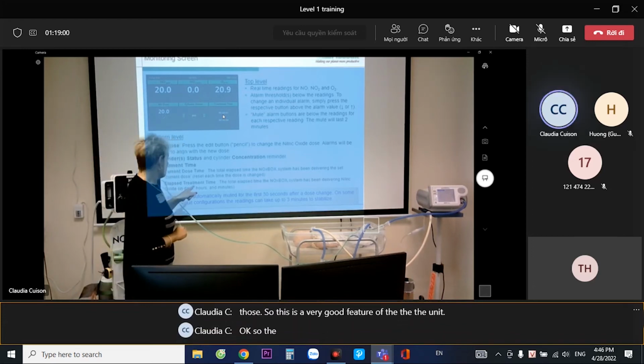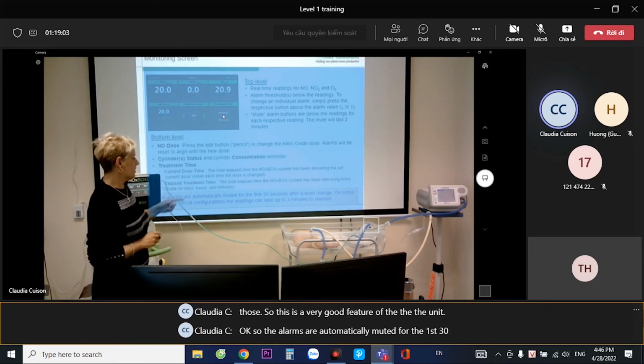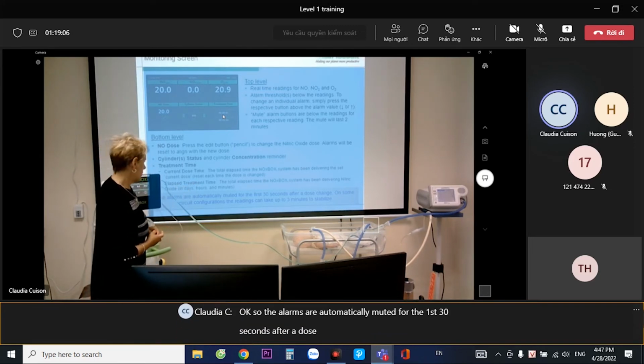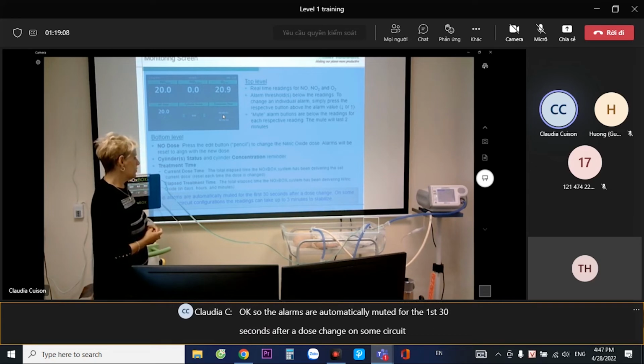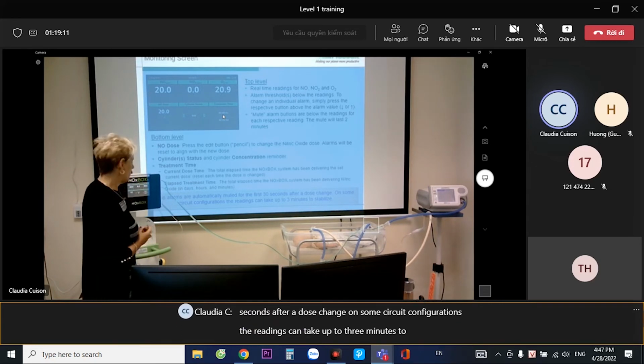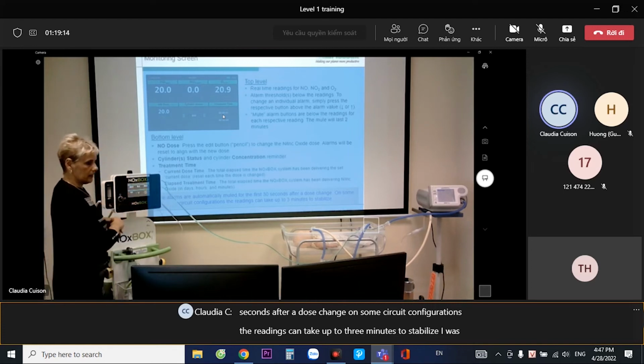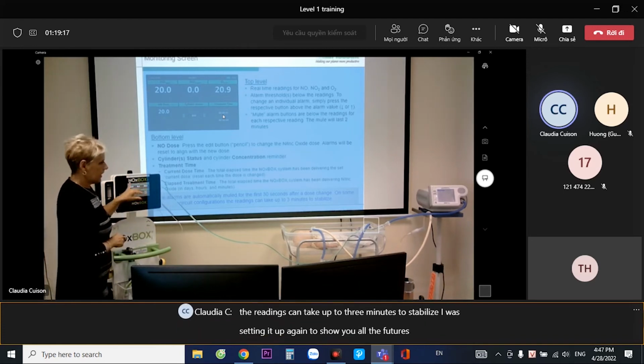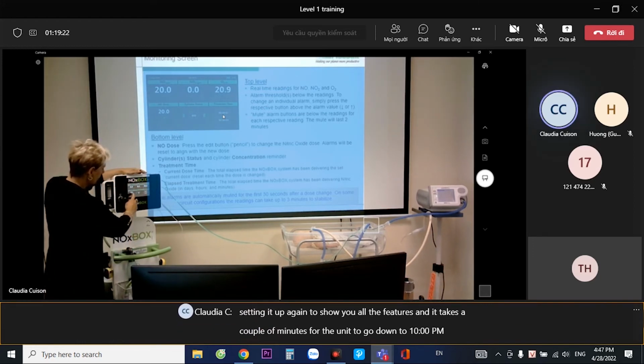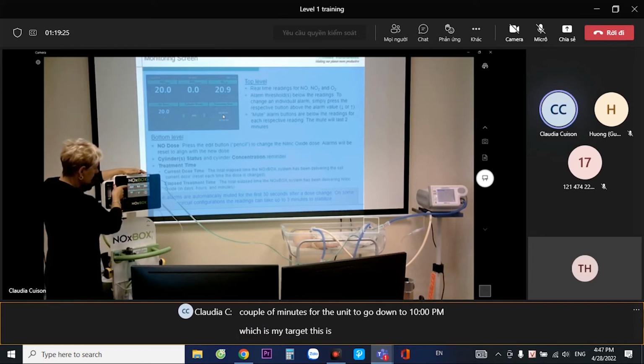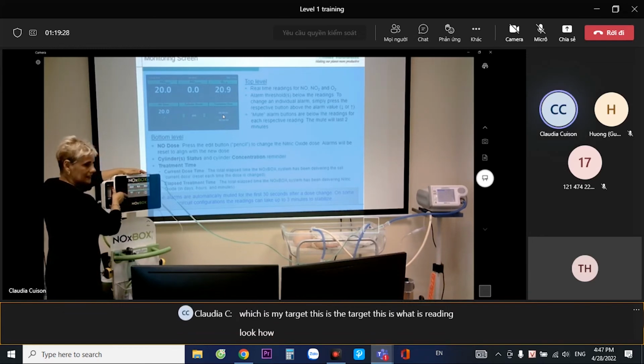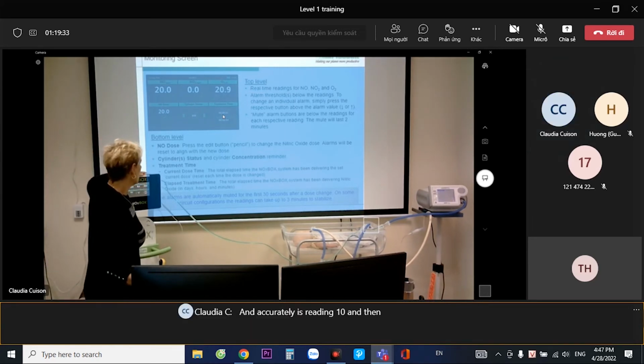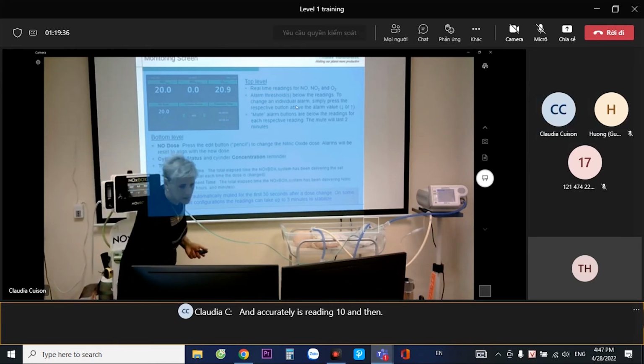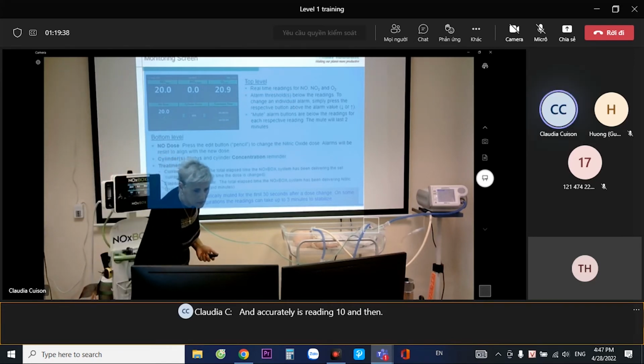Okay, so the alarms are automatically muted for the first 30 seconds after a dose change. On some circuit configurations, the readings can take up to 3 minutes to stabilize. I was setting it up again to show you other features, and it takes a couple of minutes for the unit to go down to 10 ppm, which is my target. This is the target, this is what is reading. Look how nicely and accurately it is reading. 10 and 10. I'm not having much luck with this today.